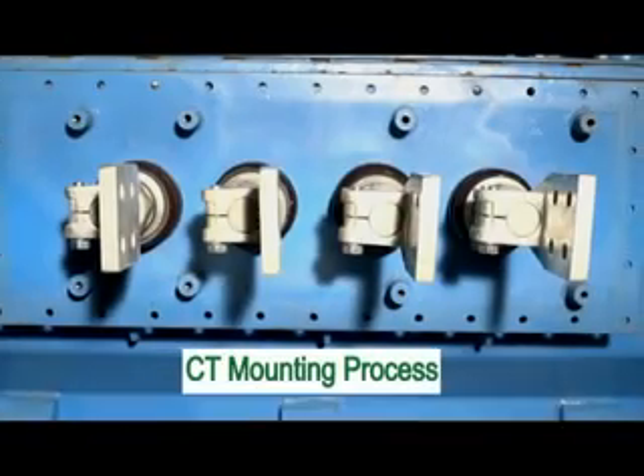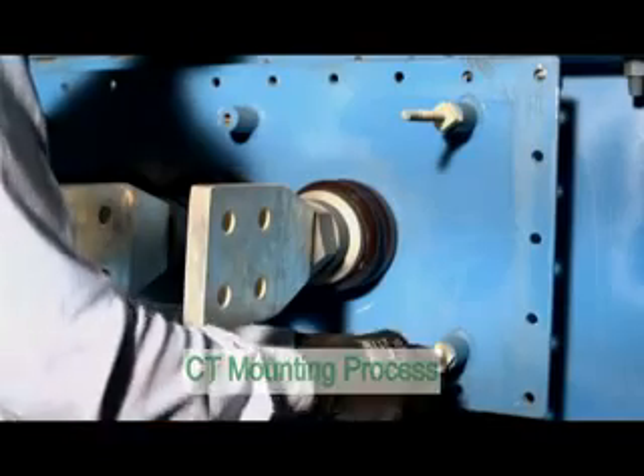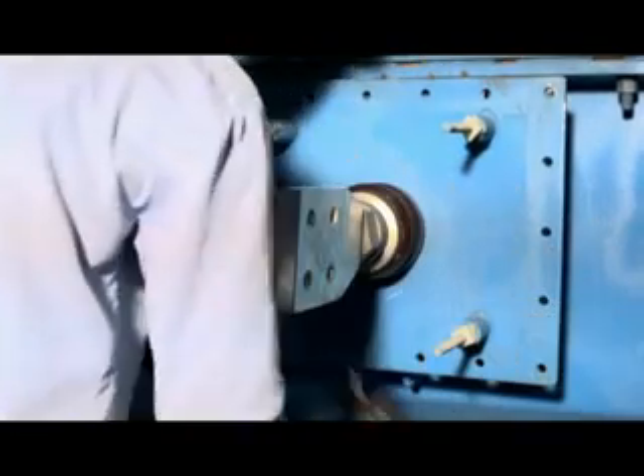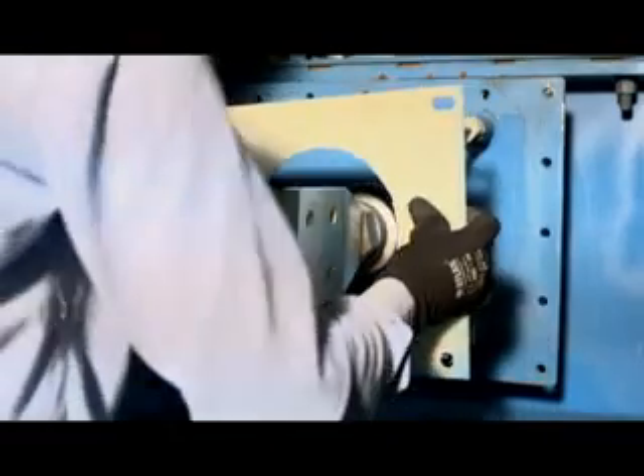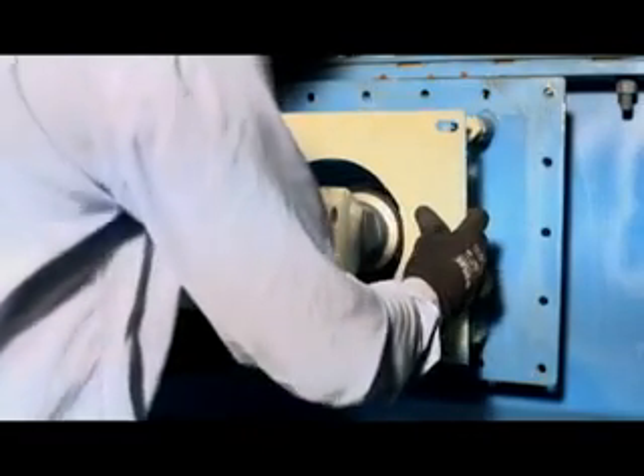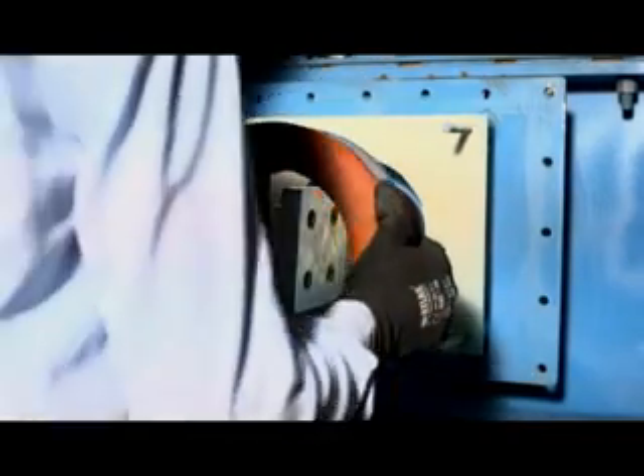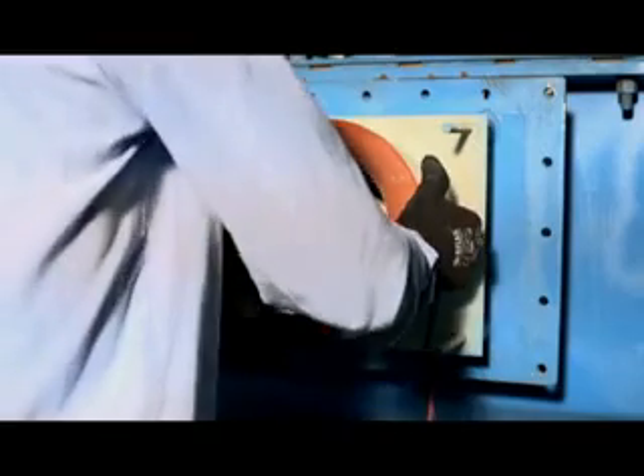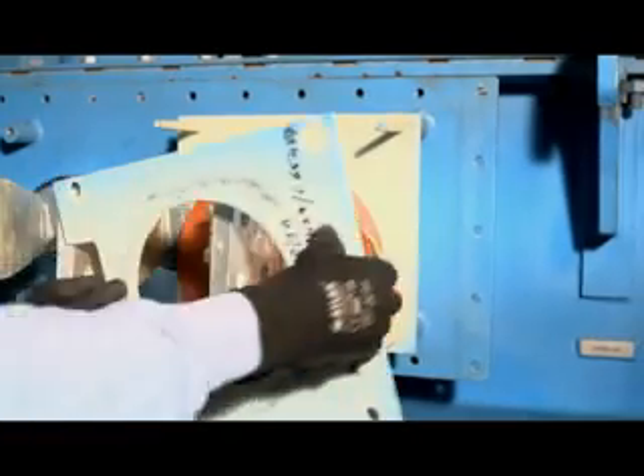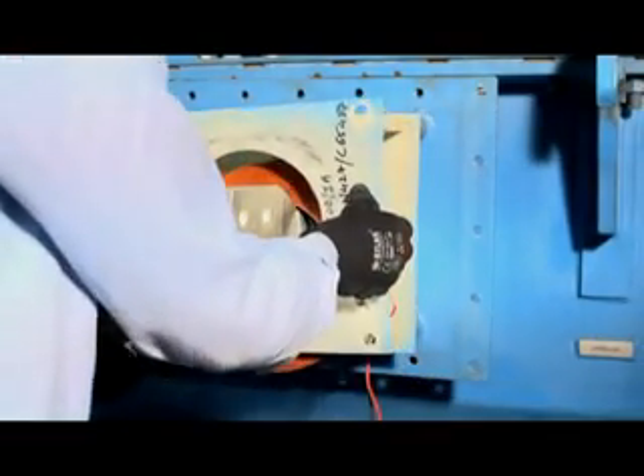Any special required current transformers are housed either in separate turrets, or on the cover plate, or as part of the core coil assembly. The secondary circuits of the current transformers are brought out in separate terminal boxes, from where the secondary is wired in the marshalling box. The current transformer can either be for protection or for monitoring, for ammeters and temperature indicators.